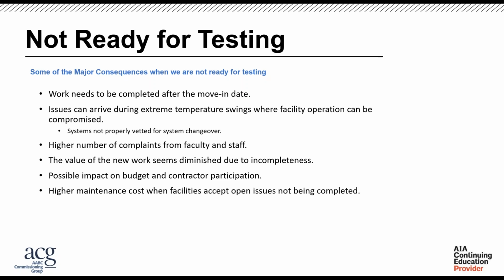times maybe we're testing in the summer, and so there's no way to test your boilers. These are things that we need to put a lot of thought into, where you're not only testing, you have to understand that you might have to come back and do some follow-up seasonal testing. You also need to think about some flexibility within the programming if some drastic temperatures come in. Those are some of the big things that I look at as well.